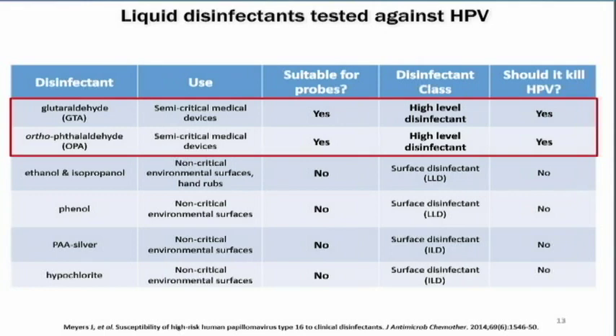So here are the liquid disinfectants that we tested against HPV. You can see the GTA, OPA, ethanols and isopropanols, phenols, PAA silver, and hypochlorite here on the left, and you can see their use. The GTA and the OPA are used for semi-critical medical devices, whereas all the rest of these disinfectants are used for non-critical environmental surfaces, or hand rubs in the case of the ethanol and the isopropanol. So which one of these are suitable for probes? Well, of course, the GTA and OPA, because these are to be used for semi-critical medical devices. They represent the class of disinfectants that we call high-level disinfectants, and by definition, they should be able to kill HPV.